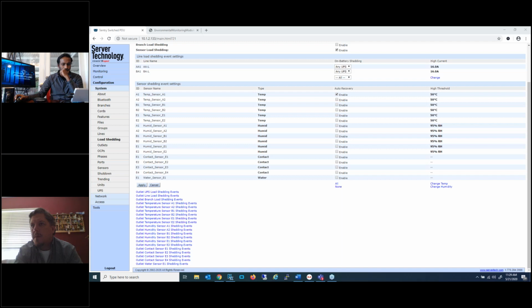Most of the people that I know that are making use of it, it is in a lab environment, other than the one large customer that specifically deploys cabinets with fans in their doors and uses this feature to switch those fans on in steps when temperature starts to rise. It's especially useful in a lights out facility where there might not be somebody nearby, and you have to roll somebody out in a truck. The PDU can attempt to save your equipment before it goes offline due to damage from an over temperature event. Awesome.